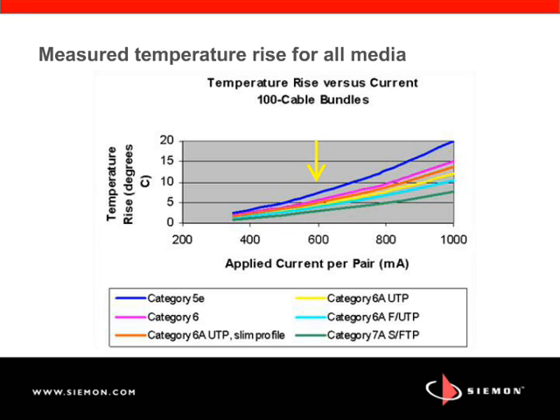As the category or performance rating of the cable increases, a couple of things happen. The conductor size gets larger, and there may be the presence of an overall foil or screen. Now this chart clearly shows that the more metal, larger conductors, and more foils or braids that are part of the cable design, the better the heat dissipation. In fact, for a category 6A F/UTP cable, the temperature rise associated with deploying a PoE type 2 application is only 3.8 degrees C.